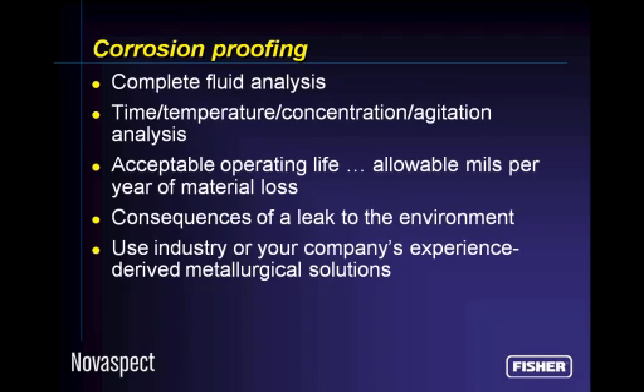Corrosion proofing is a little different. It requires that you do as complete a fluid analysis as you can regarding what's flowing through the valve. You're in control of that. Only you know what those constituents are, and it's important that you discuss with your valve supplier what those are. In the way of a corrosion analysis, you would probably do some kind of a time, temperature, concentration, and agitation analysis to know the effect of that particular fluid on the metals that we might use for construction of a control valve, or your piping system for that matter.